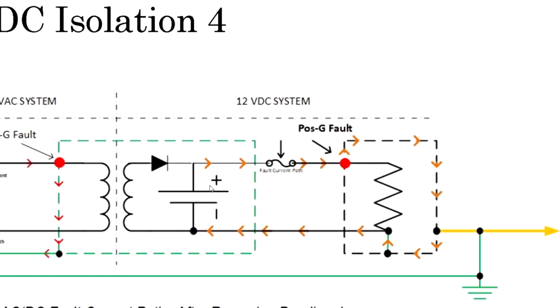Now, the one fault I didn't show would be a primary to secondary transformer fault, if 120 volts appeared over here on our DC side. Well, that's why we have to have a common ground point, and that's exactly what this does. A 120 volt fault would be returned to the utility right along through this bonding jumper that we have down here in the ground, back up to the AC panel box, and returned right back to the utility neutral. That's how we keep it isolated.